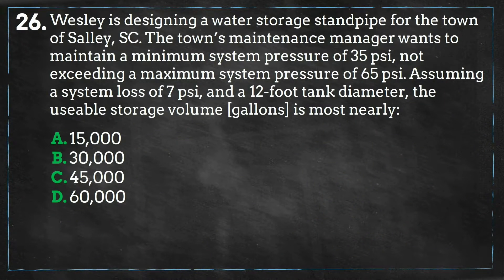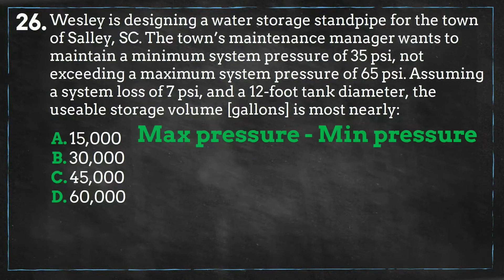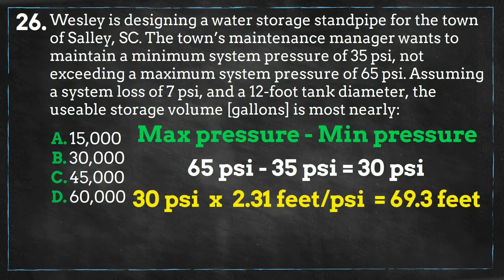We have a 12-foot diameter tank, and to find the volume of this tank in gallons, we need to determine the tank's height. We have the minimum and maximum system pressure requirements and know how many feet of head it takes to achieve those pressures. We are not interested in the total elevation of the tank, so the system's pressure loss will not be a factor. We only want the tank's height, so we take the difference of the system pressure minimum and maximum, which equals 30 PSI, multiply by the factor of 2.31 feet per PSI, and get the height of the tank, which equals 69.3 feet.